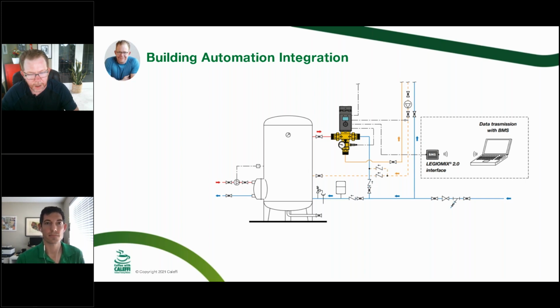And if you're dealing with a hospital or a school or anything where you've got sensitive people in the building, again, this is an insurance policy. The protection from a liability standpoint is absolutely important. Yeah, and Modbus and BACnet options, depending on what your language is. But then read-write too, so the automation company can decide to push all those different parameters into a disinfection mode.